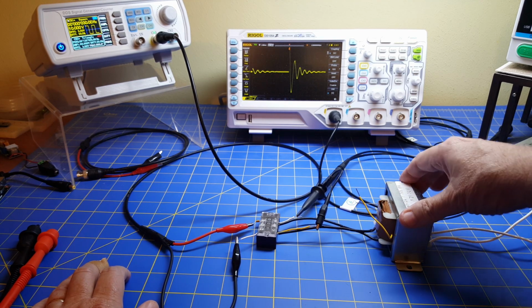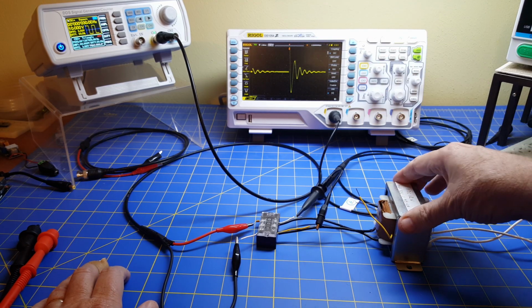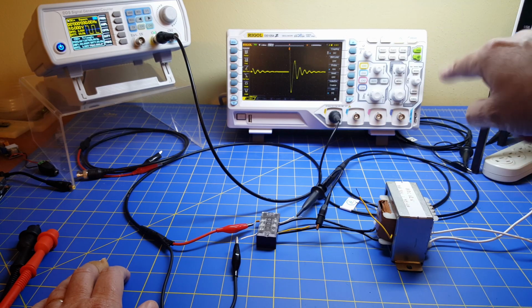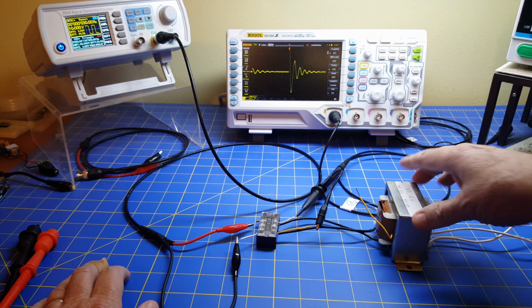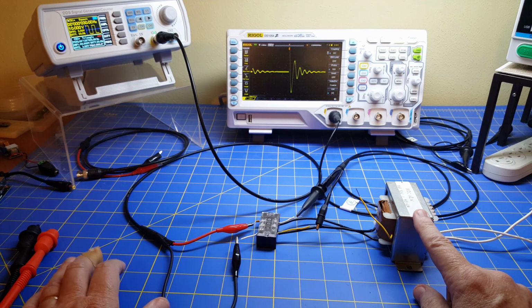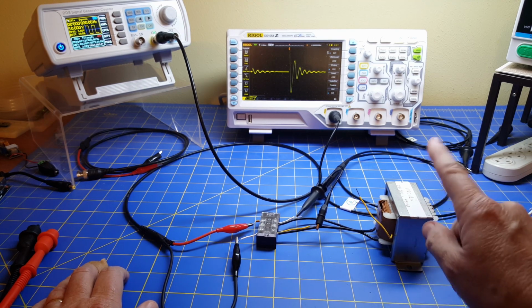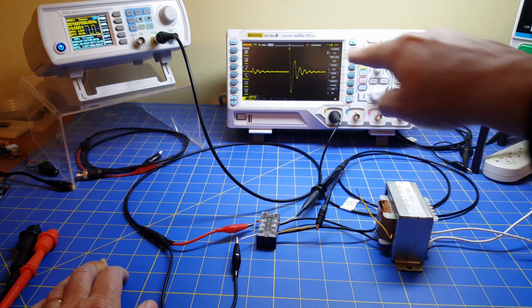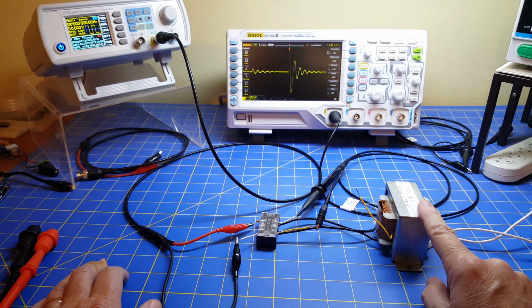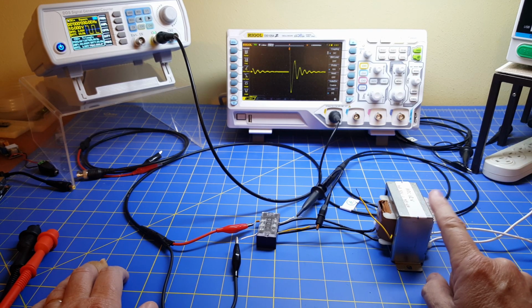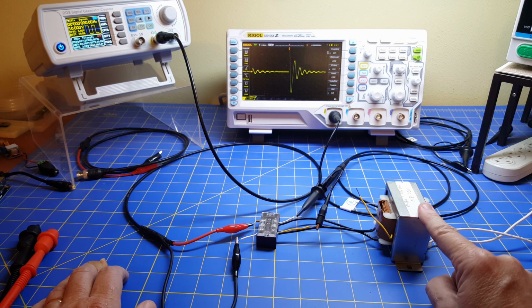So the concept is, like we said, if there are few rings and it's damped, it probably means it's a bad transformer. If there are a lot of rings and it's not very well damped, it probably means it's a good transformer with no short circuit. The basic question is, is this a good transformer? Even if you're looking at that damped trace, with those oscillations, does this mean it's a good transformer or is it a bad transformer? Think about it and answer it to yourself. It's got maybe one, two, or three rings. Is that a good transformer or a bad transformer?